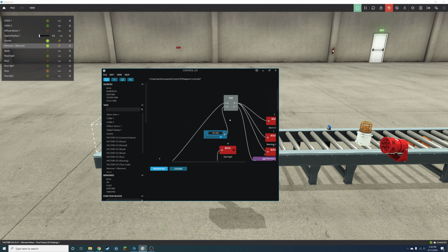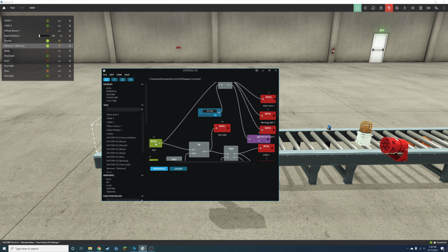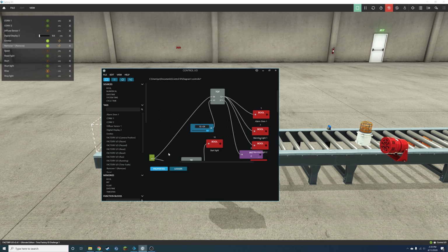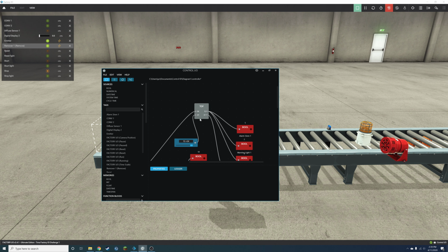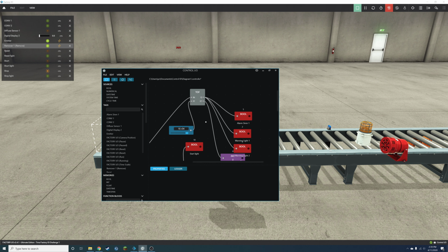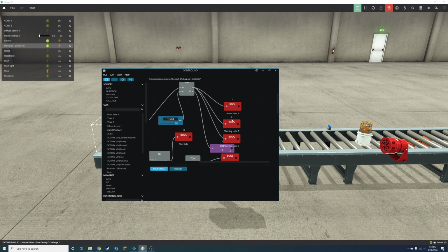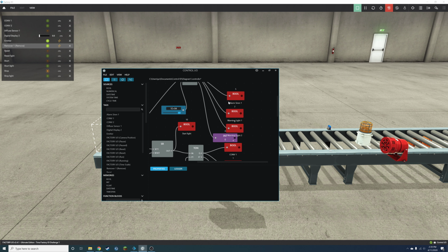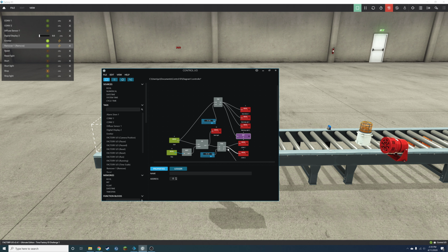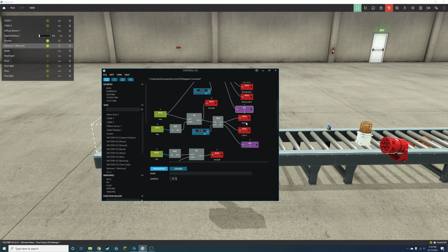on. This is a timer off delay, so when this start button, since it's non-retentive, you turn it on, it's going to immediately shut off. For 10 seconds, you're going to have this alarm and these warning lights going to run. And then, since this is going to be happening at the same time, our conveyors are going to start. So, why don't we see how that works?